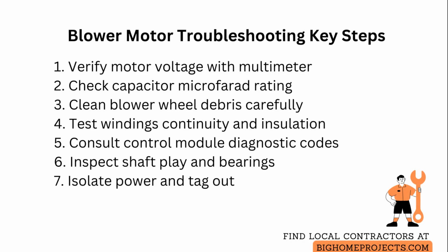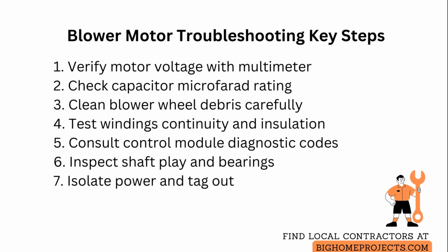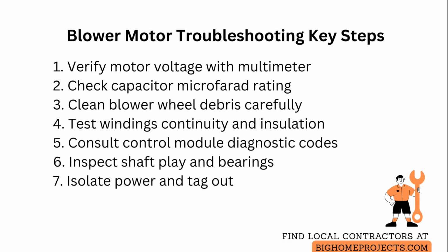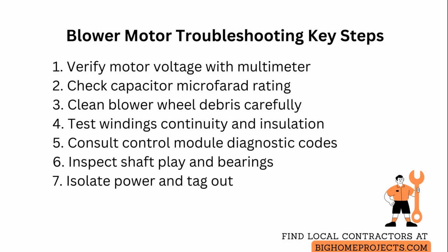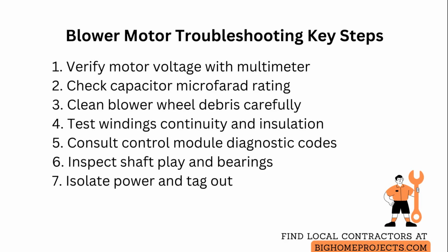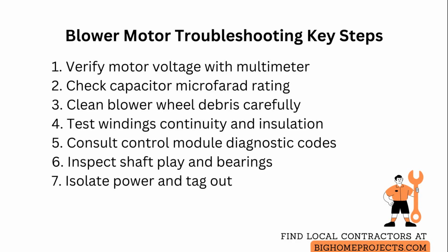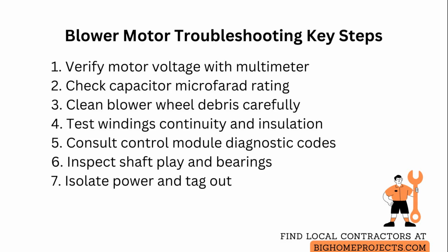more than 10%. Inspect the blower wheel for debris, bent fins, or rubbing that will cause noise and reduced airflow, and carefully remove and clean with a soft brush while supporting the wheel to avoid bending. Test the blower motor windings for continuity and for insulation breakdown using a megohmmeter if available, and compare readings to the manufacturer specifications to determine if rewind or replacement is required.